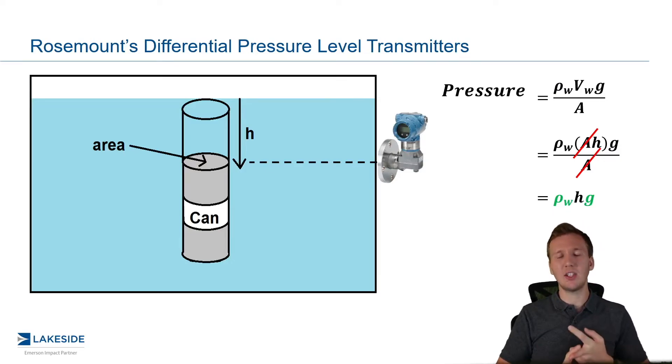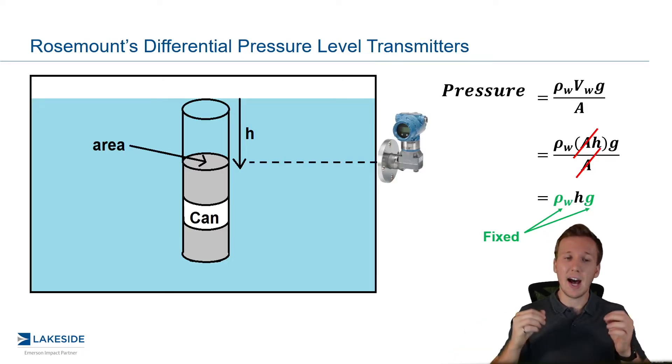Now, why do I have density and gravitational constant in green? It's because both of these are fixed. Now fixed, but not necessarily constant. Gravitational constant is relatively constant, as the name would imply. The density is not. The density, we have to fix it in order to configure a DP level transmitter.